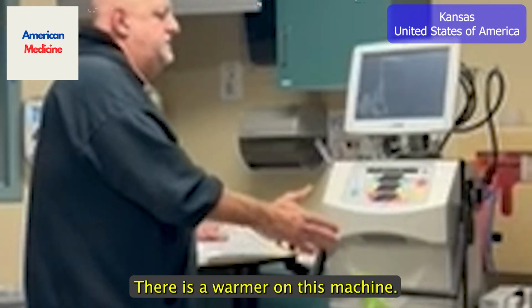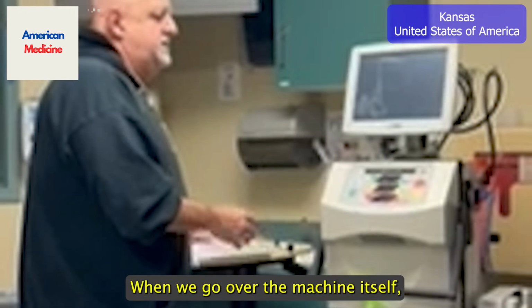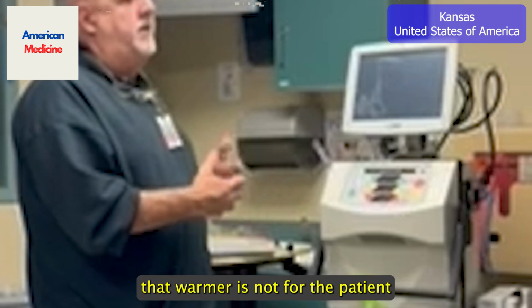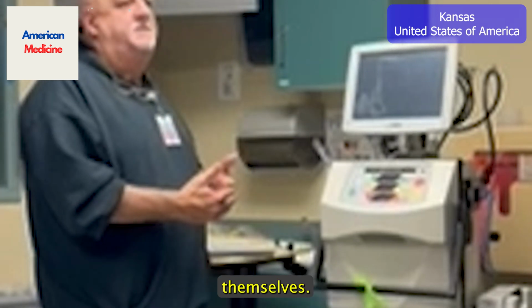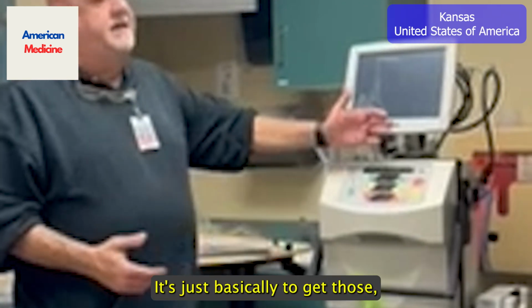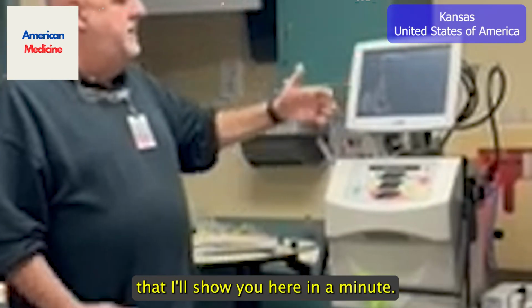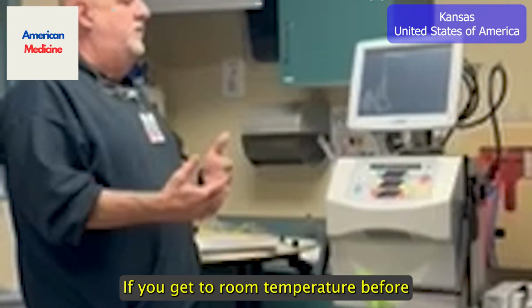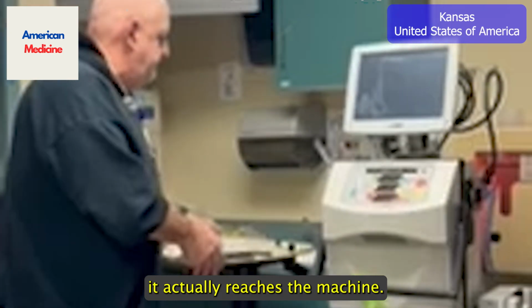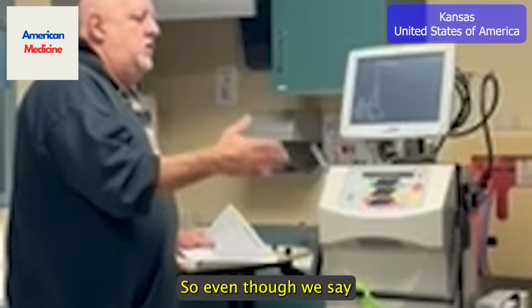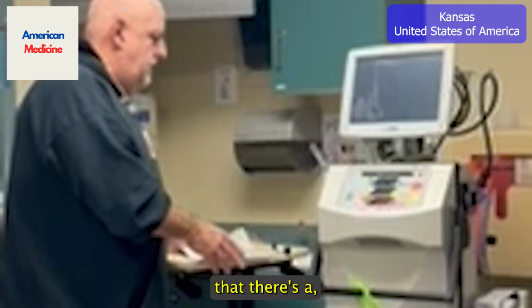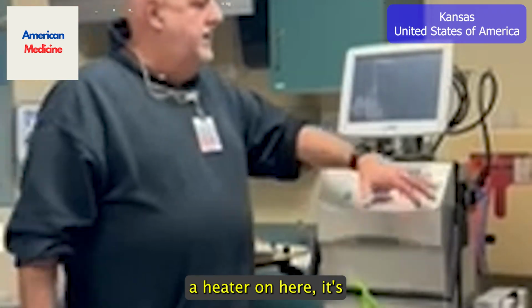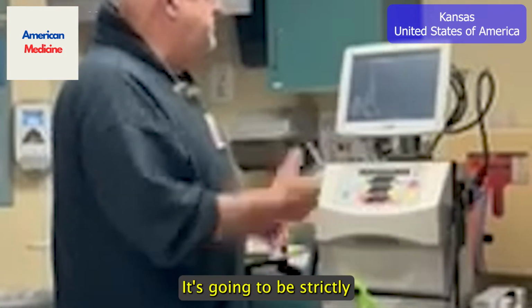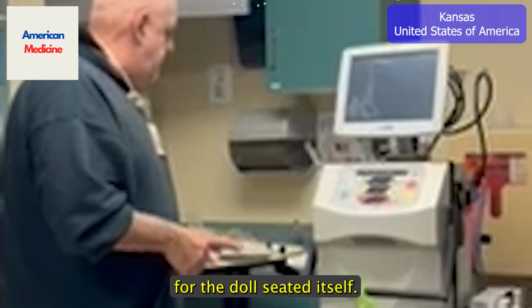There is a warmer on this machine. When we go over the machine itself, I will show you, but just remember that warmer is not for the patient themselves. It's just basically to get the PrismaSol that I'll show you in a minute to room temperature before it actually reaches the machine. So even though we say that there's a heater on here, it's not for the patient. It's going to be strictly for the dialysate itself.